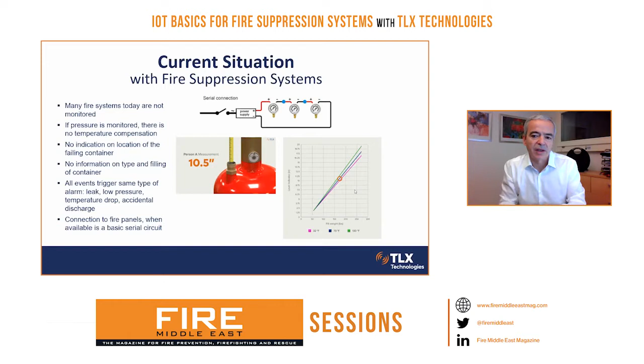Today, technology allows us to collect a number of different variables in a system that let us redefine how we monitor and service our installation. For example, we could measure pressure and compensate that pressure with the temperature in the same sensor. We could measure liquid level electronically, and we could have the precise location of each cylinder. So when an event is recorded, we'd know exactly which cylinder has the problem and what the problem is, because the alarms would tell us low pressure, discharge, or whatever it is.